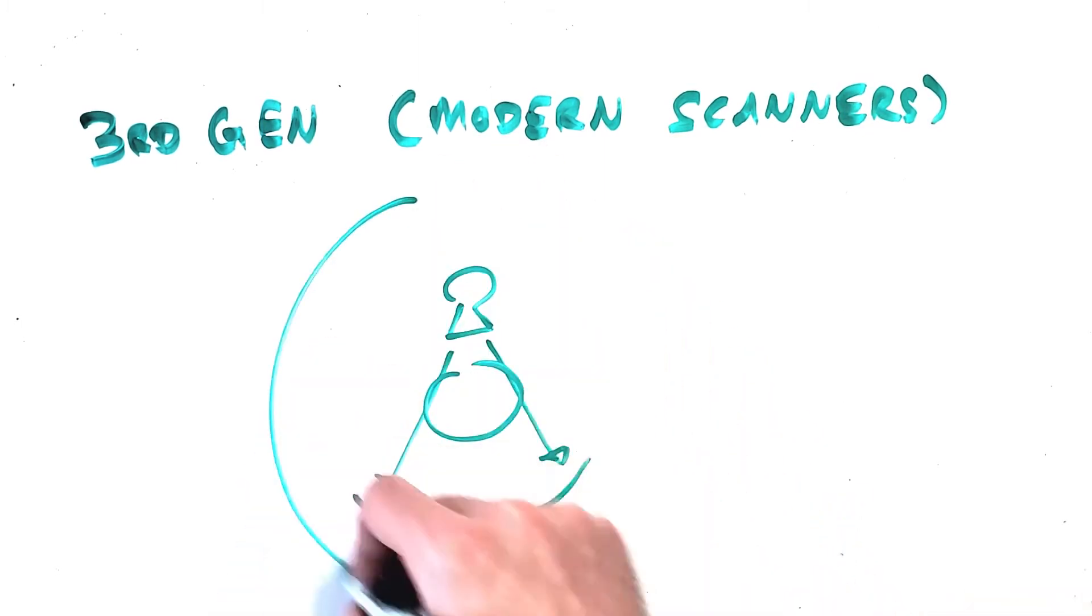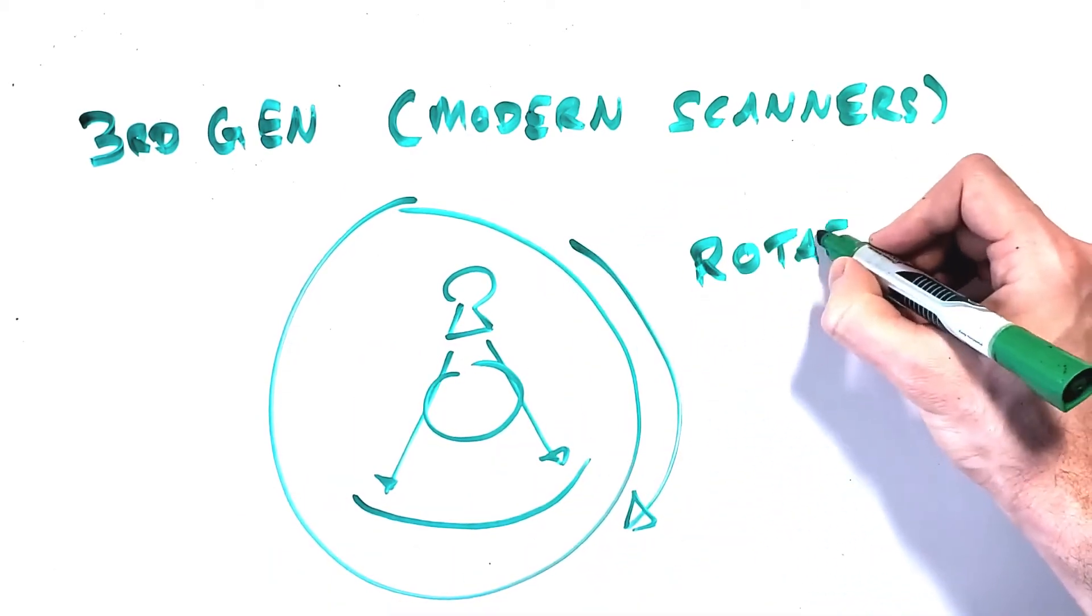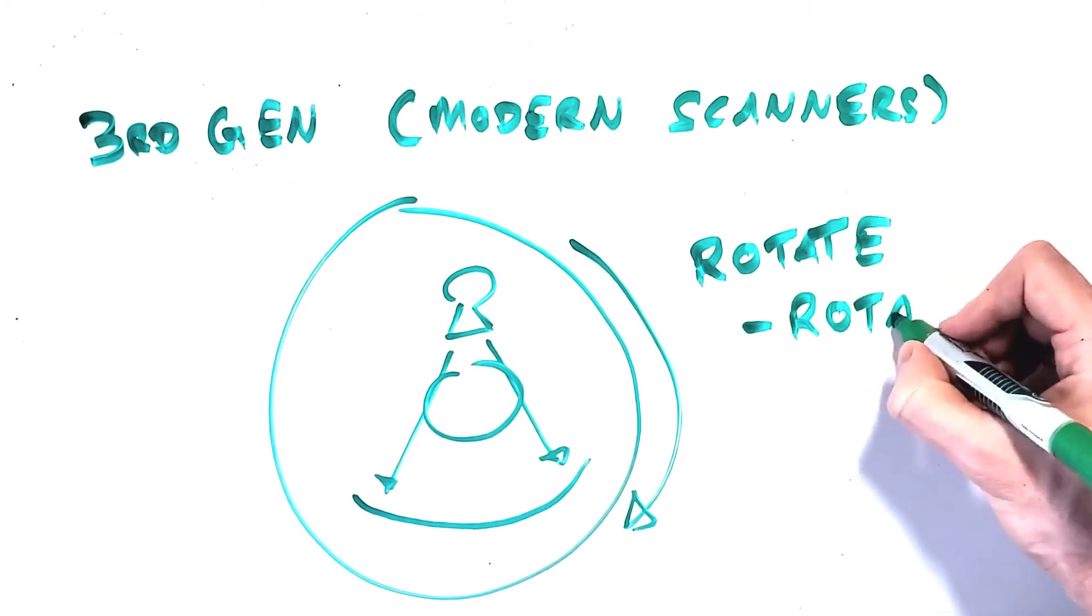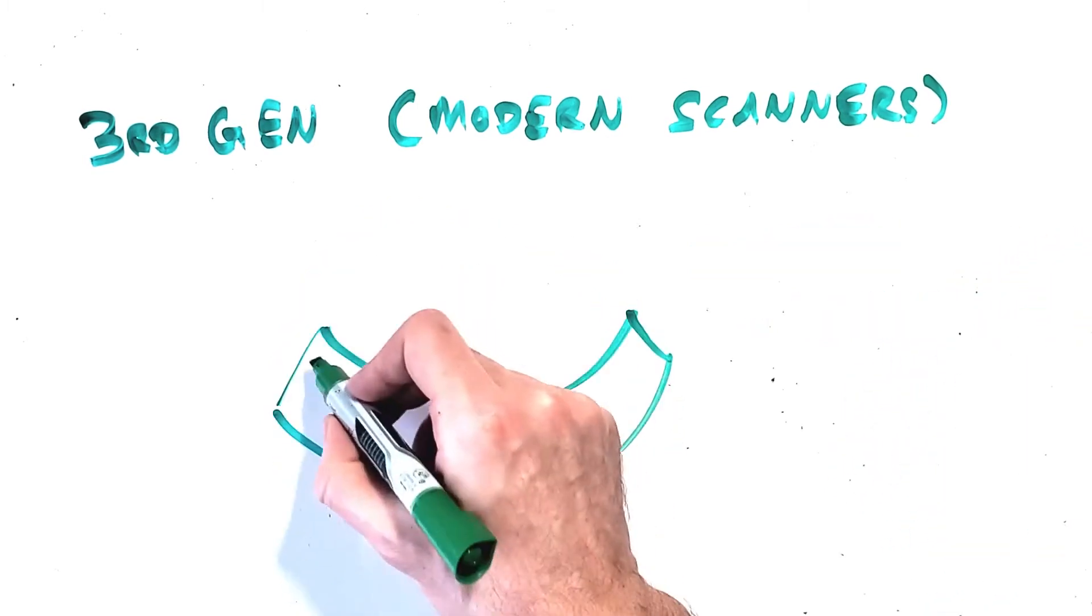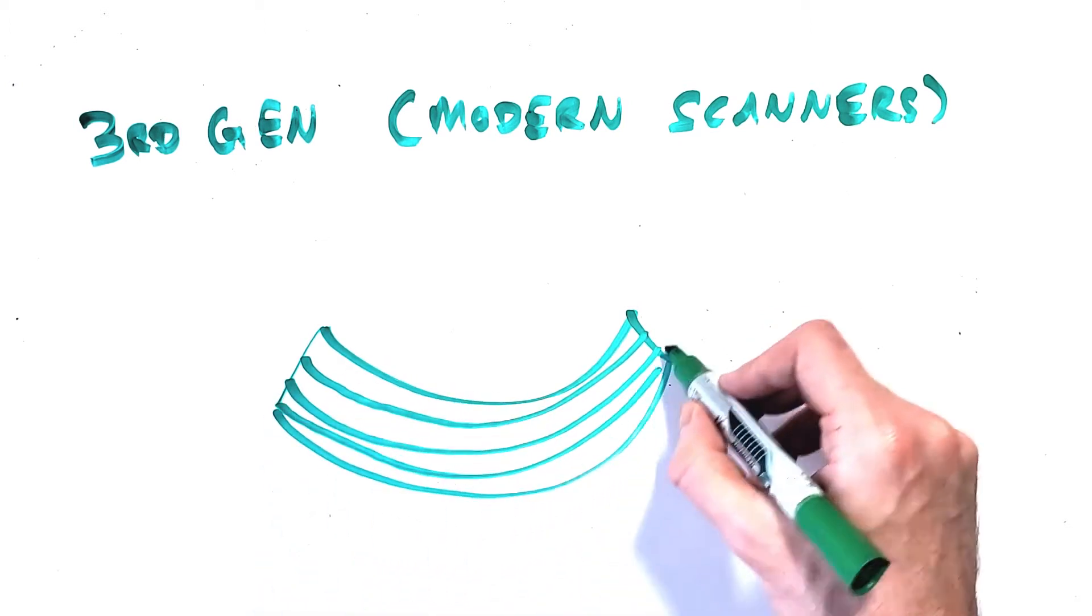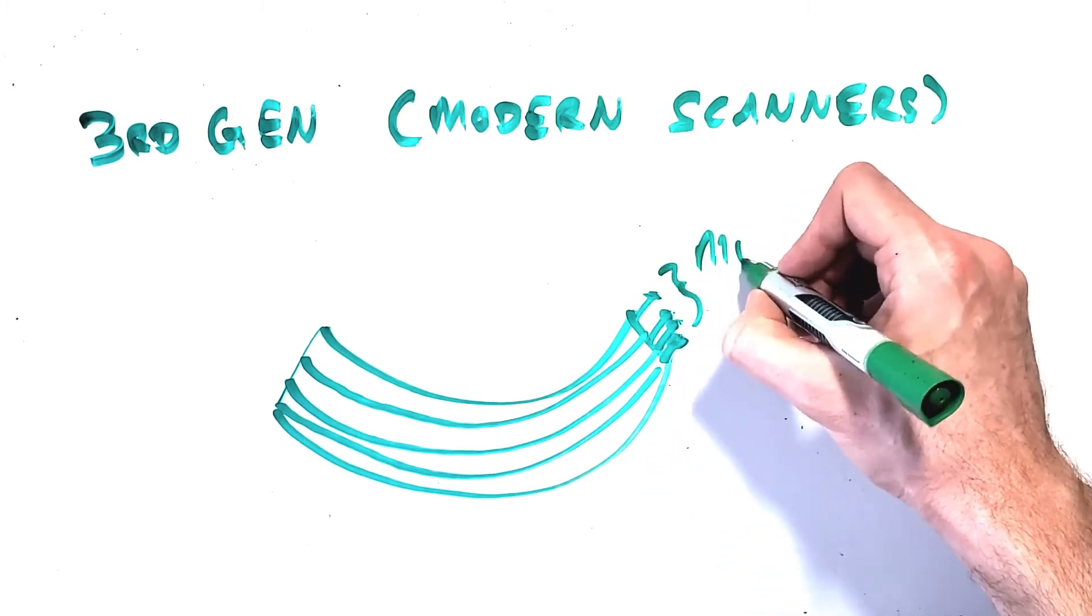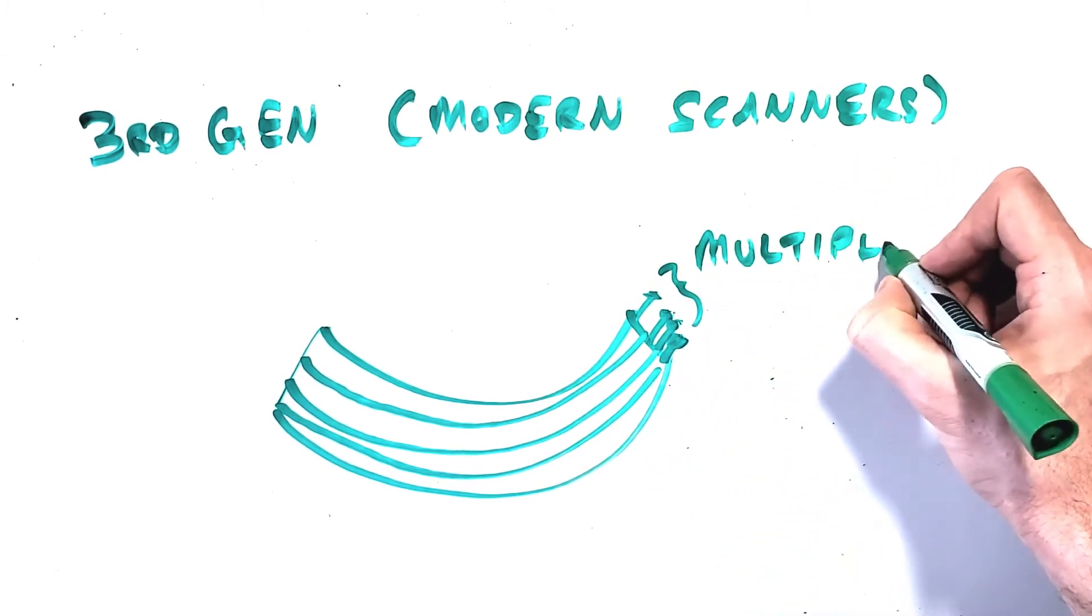We've upgraded the single slit-shaped fan to a thicker fan beam exposing a multi-row detector, where the detector, instead of being a single row of detector elements, is now composed of multiple rows of detector elements, so it looks more like a curved version of a conventional digital radiography detector, just much wider than it is long.